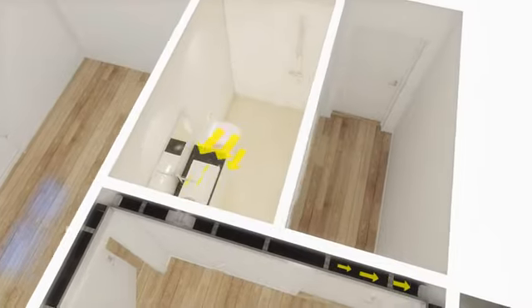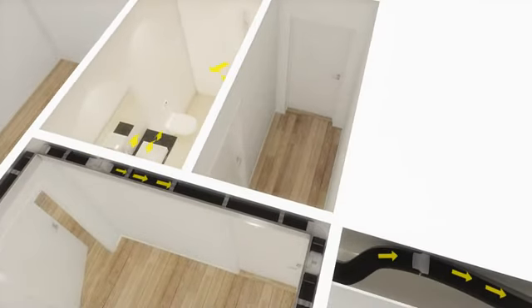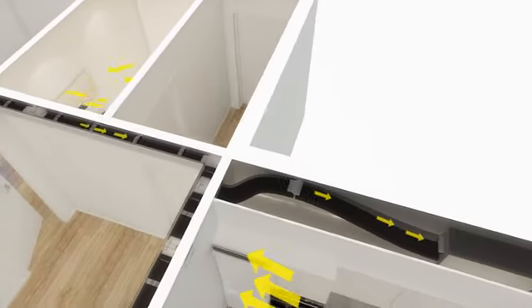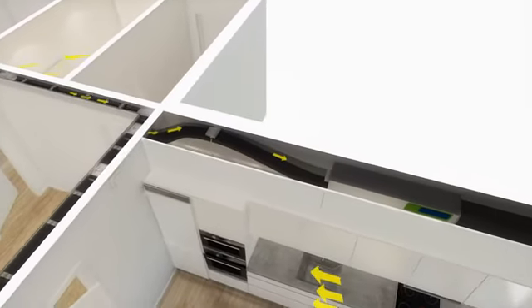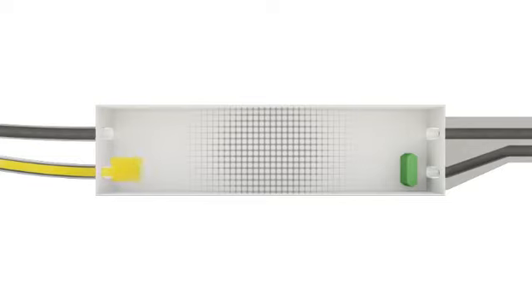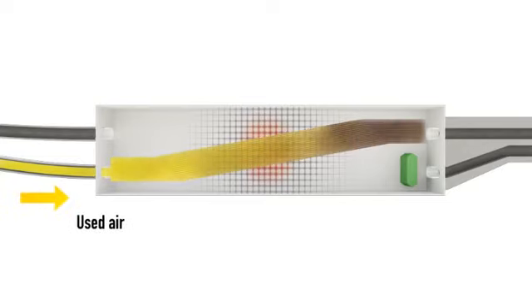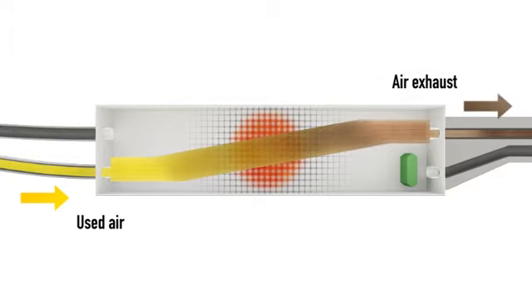When the system is in operation, the used and damp air is extracted out of the bathroom and kitchen and directed through the ducts into the air handling unit. The used warm air is then directed through a series of metal lamellas in the cross-current heat exchanger, thereby heating up the metal lamellas in the air handling unit. The used air is then expelled outside.